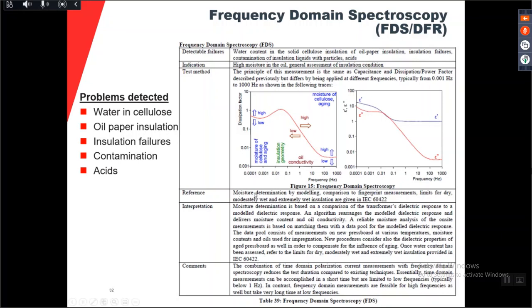You get the moisture determination by modeling. Comparison to fingerprint measurement is not really accurate, I would say. And then you can determine whether your transformer is wet, dry, or how it is. The moisture determination is based on the transformer's measured response compared to a modeled response. This is all very well examined and described in IEC 60422 and also in a technical brochure. I don't really remember the name now, but I can send it out.